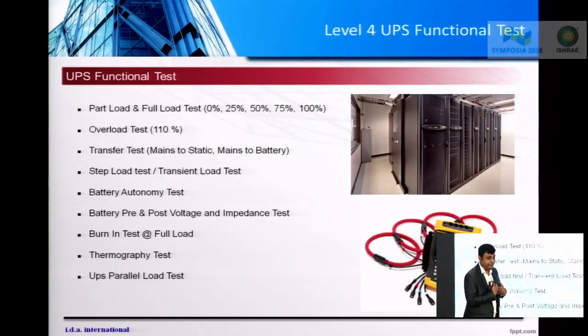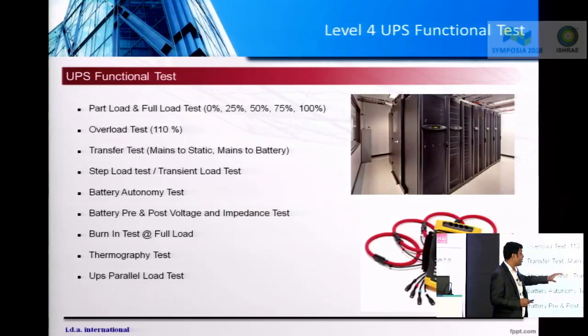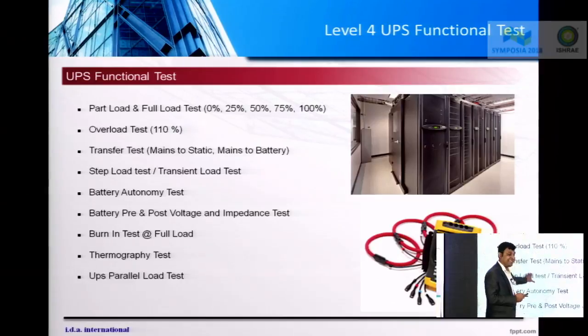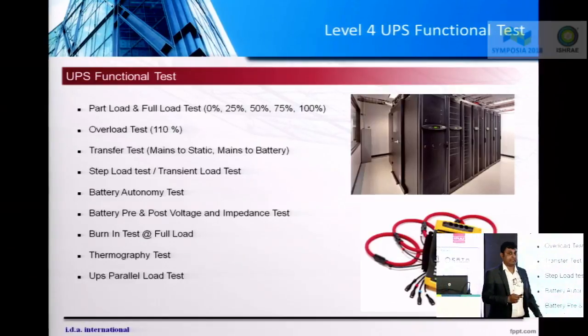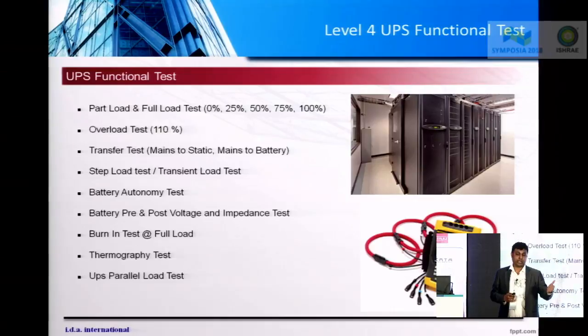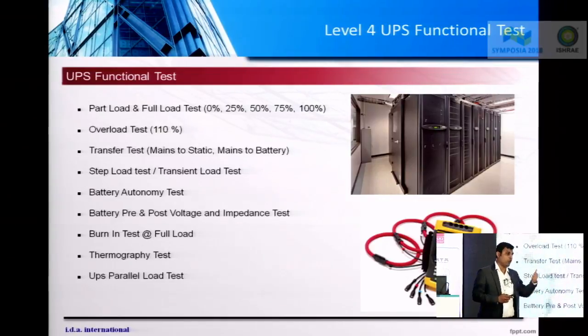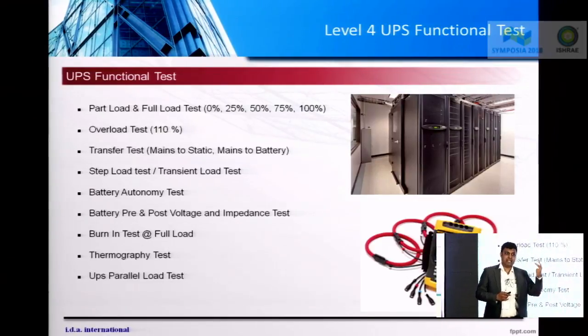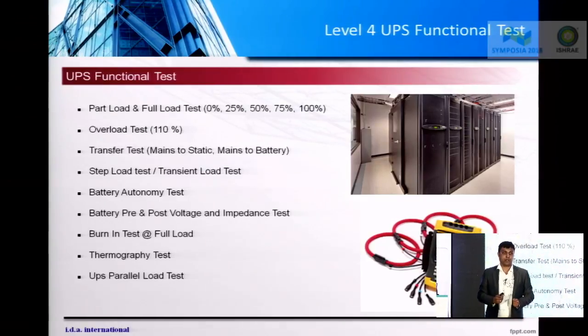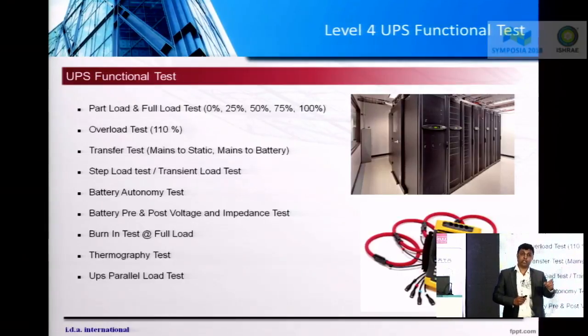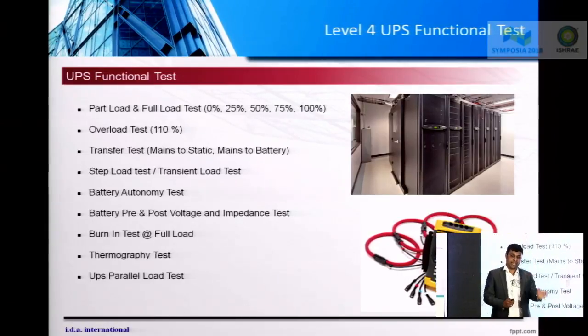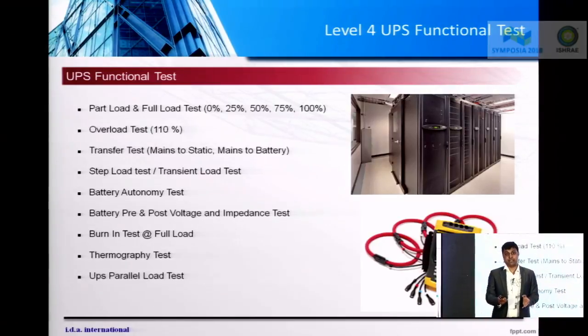If I have to verify the performance of UPS, I have to ensure that I take the following steps. The first thing I have to verify is I load the UPS to its part load condition and verify its efficiency. I will load it to 25%, 50%, 75%, and I will verify it provides the efficiency as mentioned in the technical catalog. The second thing I will do is load the UPS to its 100% capacity, and again verify the input-output parameters and verify it gives the right efficiency, what has been stated in the technical data sheets.